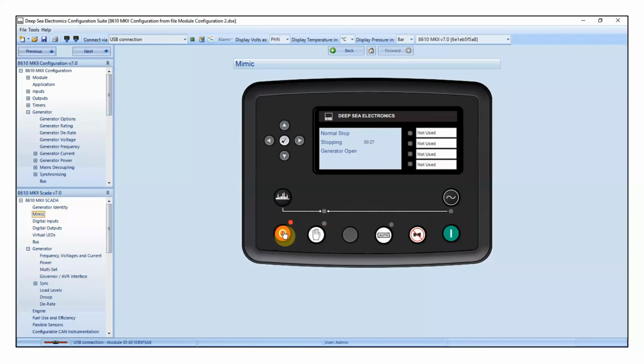It's very, very simple. All you've got to do is start the generator, leave the breaker open, and then adjust the switch 1 value for the governor first until you get to 50 Hertz or whatever your nominal frequency is, and then adjust switch 1 of the AVR until you get to nominal voltage, whatever that nominal voltage may be. Again, pay very close attention: if you increase switch 1 and the frequency or voltage goes down, pay attention to that. I'll show you in the next video what happens if we don't fix that problem, and also what to do if you do see that.